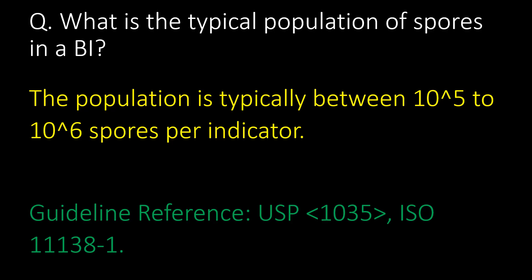What is the typical population of spores in biological indicators? The population is typically between 10^5 to 10^6 spores per indicator. Reference guidelines: USP chapter 1035 and ISO 11138-1.